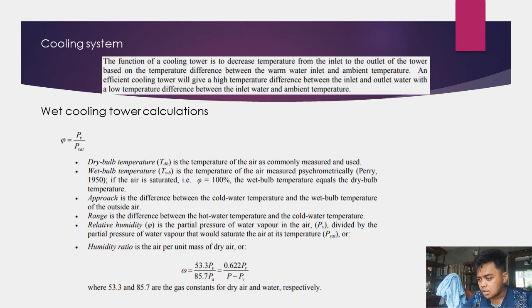Wet cooling tower calculations. Phi is equal to P sub V over P sub sat. Dry bulb temperature is the temperature of the air as commonly measured and used. Wet bulb temperature is the temperature of the air measured psychrometrically. If the air is saturated, Phi is equal to 100%, and the wet bulb temperature equals the dry bulb temperature. Approach is the difference between the cold water temperature and the wet bulb temperature of the outside air. Range is the difference between the hot water temperature and the cold water temperature.